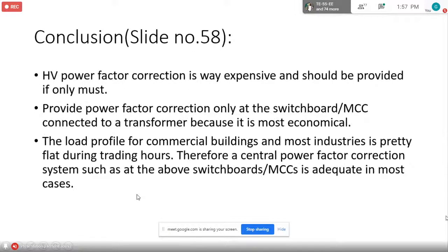Conclusion. HV power factor correction is very expensive, and should be provided only if a must. Provide power factor correction only at the switchboard MCC connected to the transformer because it is most economical. Don't provide it at the motor or distribution board. Very, very expensive and a maintenance nightmare. The load profile of commercial buildings and most industries is pretty flat during trading hours. Therefore, a central power factor correction system such as above switchboards MCC is adequate in most cases. Most of the load profile is very, very flat.